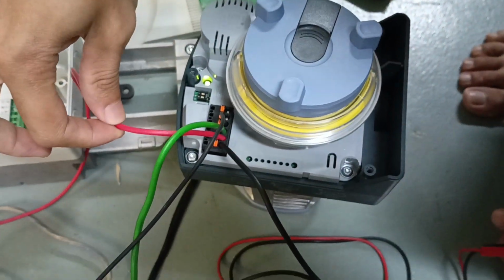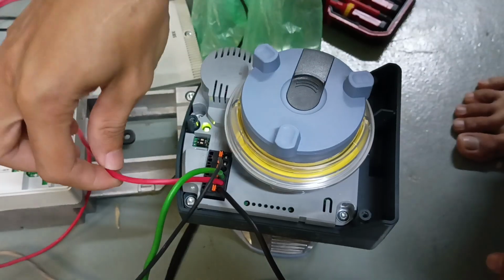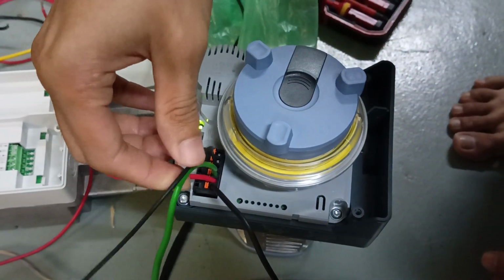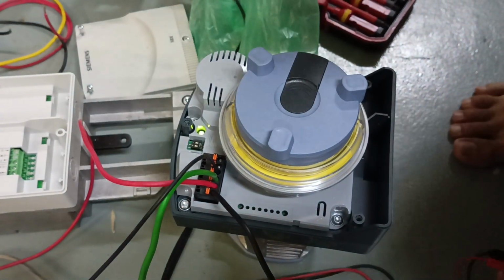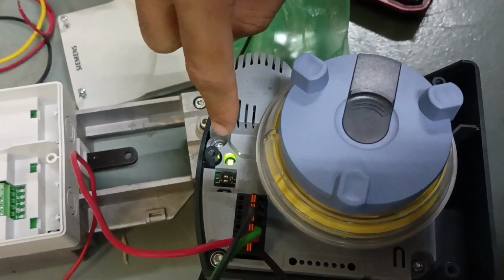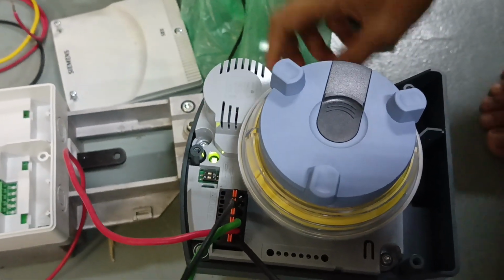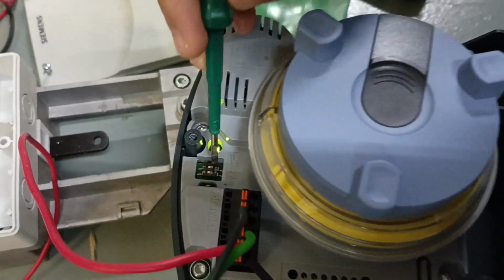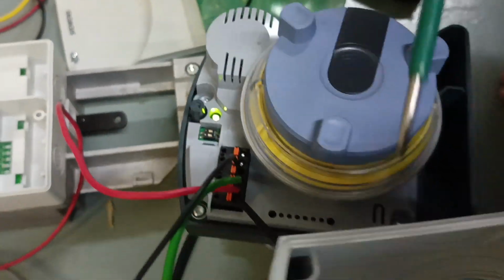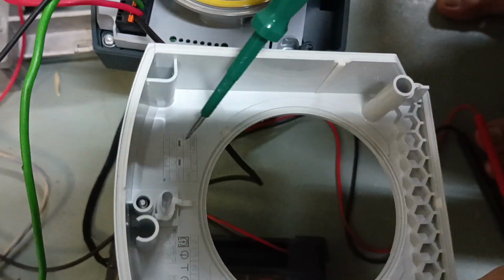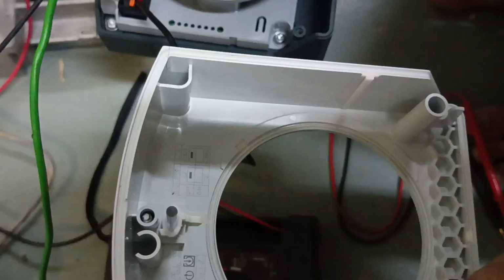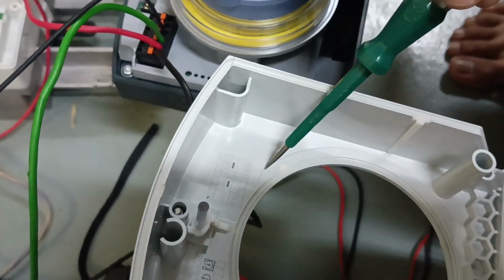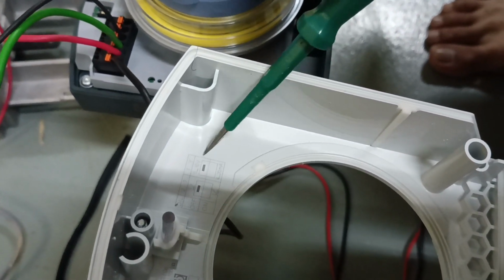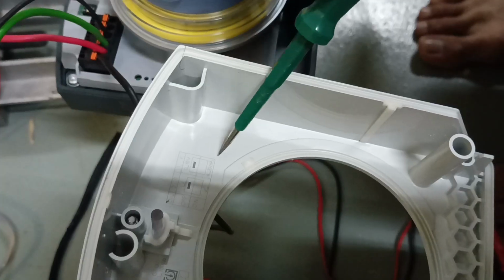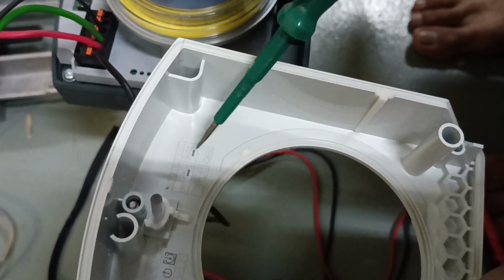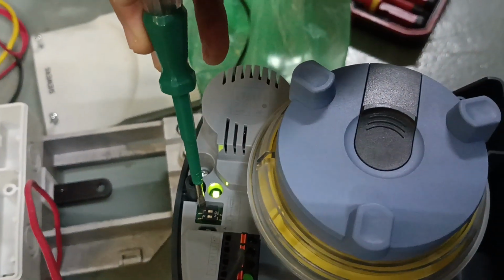First we check power, and after that, if there is power, we check for the 0 to 10 signal. If there is, the LED should be on. One more thing, here we have a dip switch. The info for the dip switch is behind this actuator cover. Number 1 is for choosing either a 0 to 10 signal or 4 to 20 milliamp. The factory default is 0 to 10.